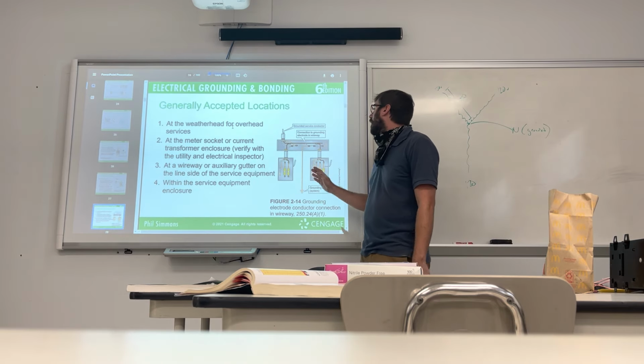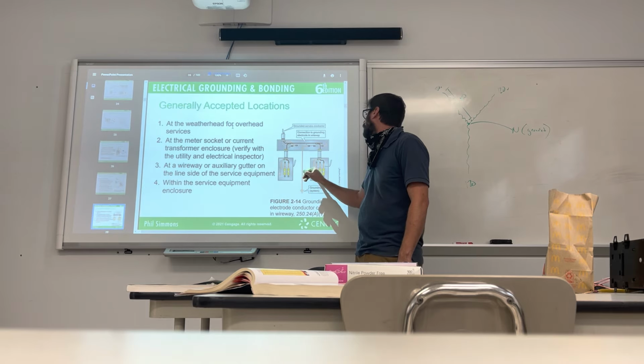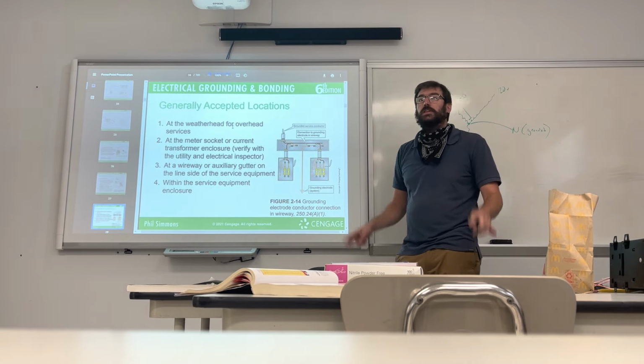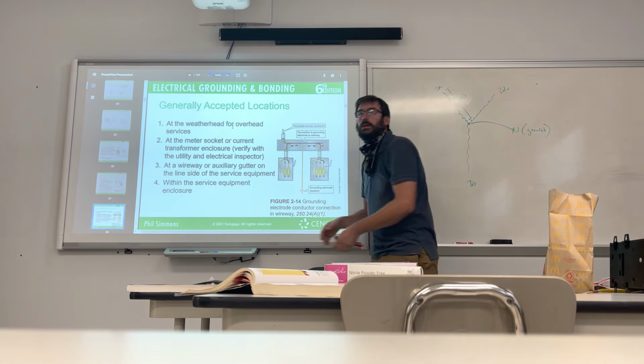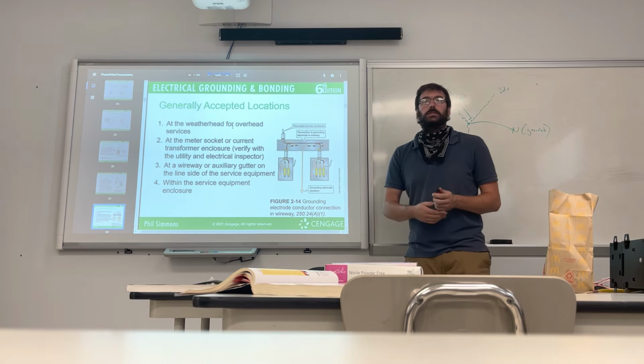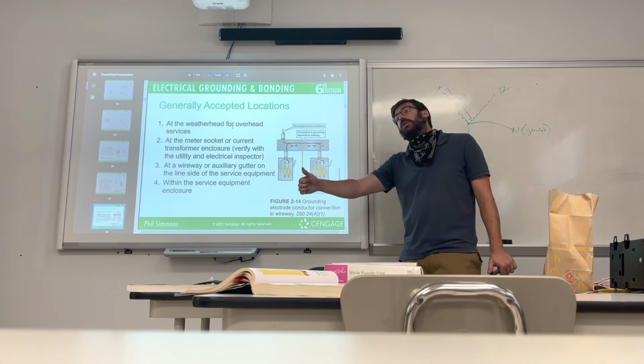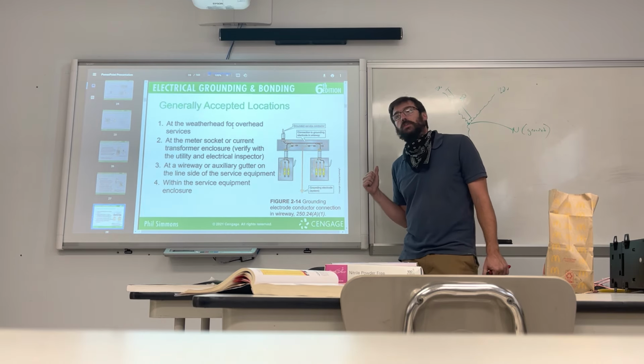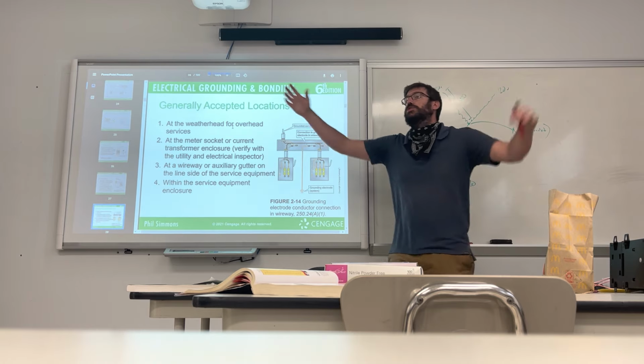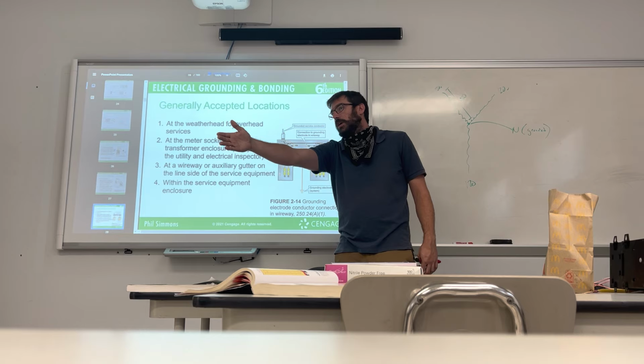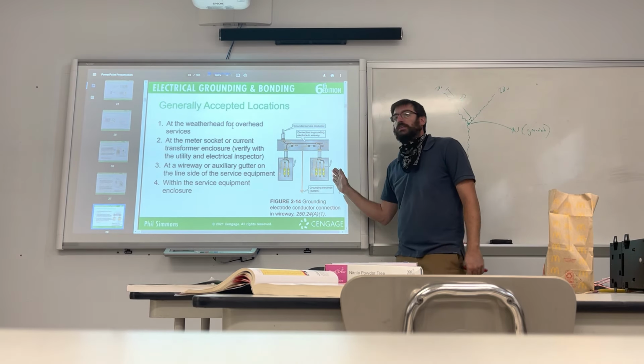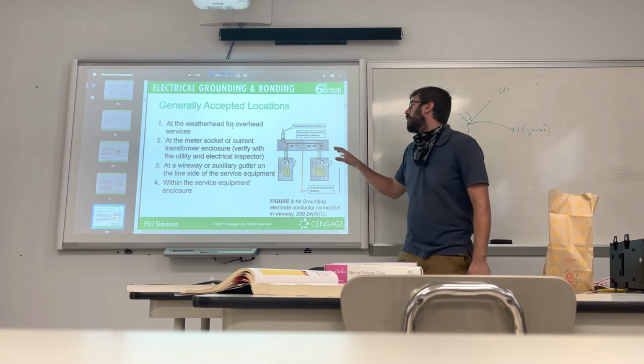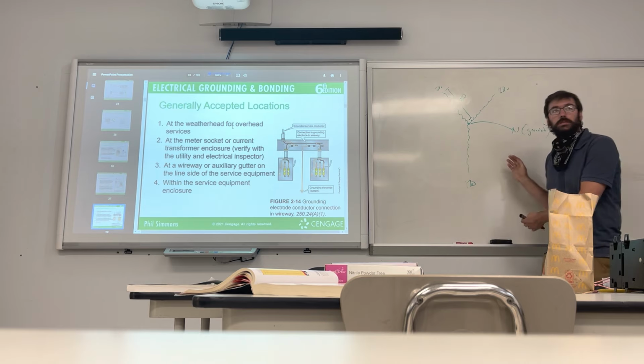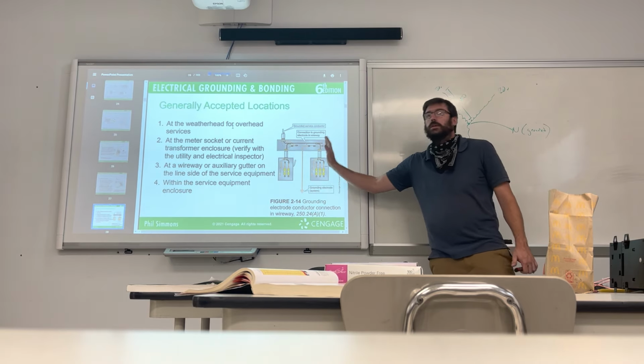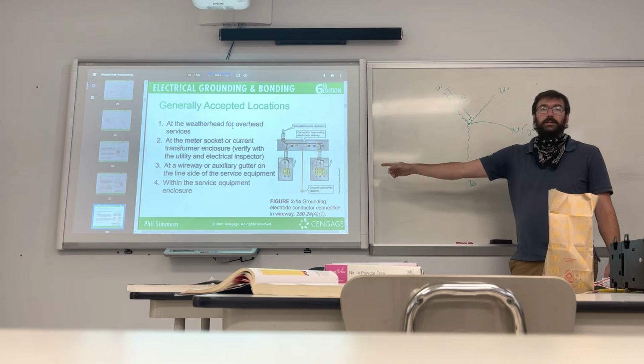No, I'm not. Now you're going to see that the ground is on that neutral, and the ground is on that neutral as well. Because if you think about it, these are both main breakers, or they're both main disconnects. They both have an even shot of power. Before, why wasn't the sub panel like that? Because the sub panel was dependent on what for power? The main panel box. So the sub panel is just a large circuit, and you would never put the ground and the neutral together on an outlet, would you? Well, you wouldn't on a large circuit. But here, think of these as a main panel box. So there are instances where you can have a trunk feeding 1, 2, 4, 7 of these. The neutrals and the grounds have to be bonded in it because we're thinking of each one as a main breaker or a main disconnect.